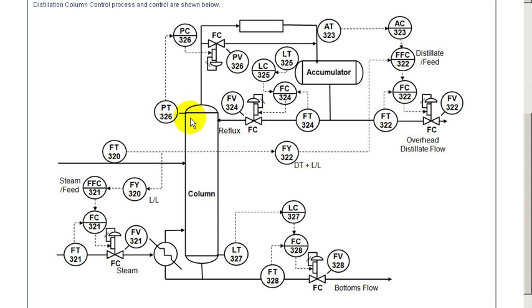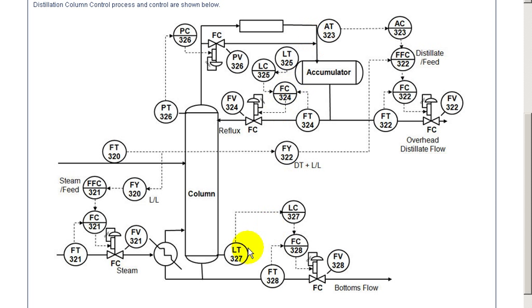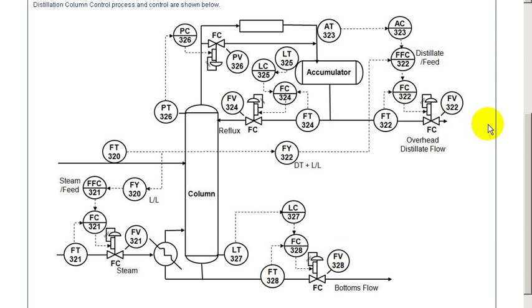The pressure is very critical to maintain constant pressure. We adjust a bypass around the heat exchanger. The level of the bottom of the column is maintained by adjusting the material removed at the bottom, the bottoms flow.